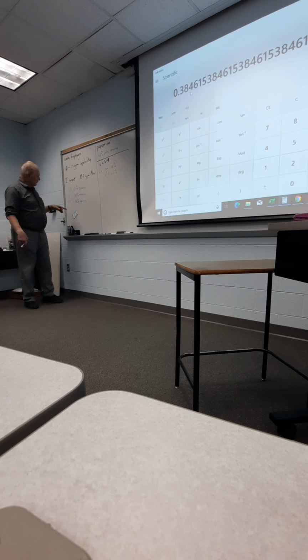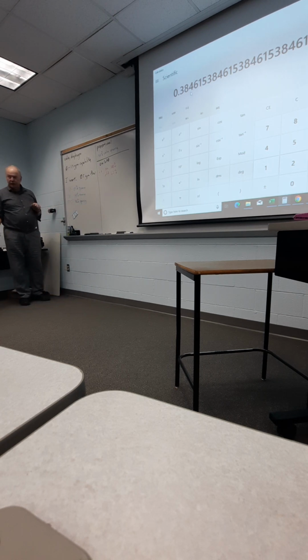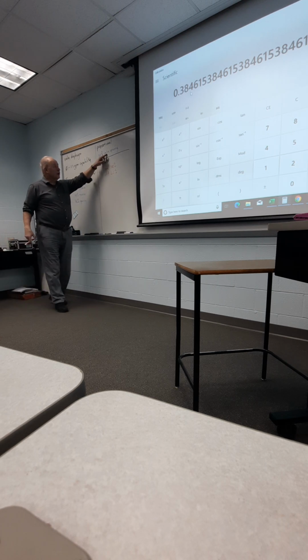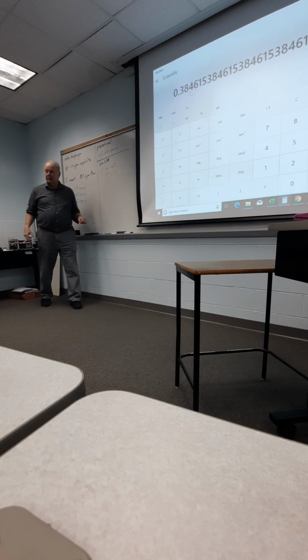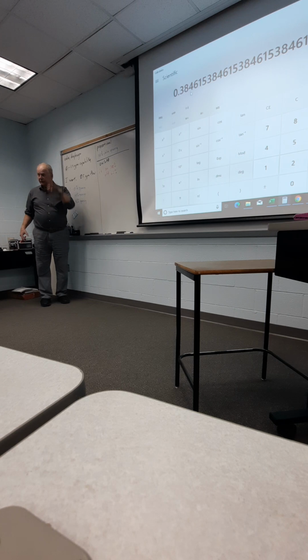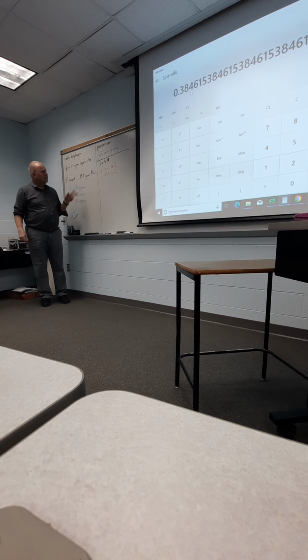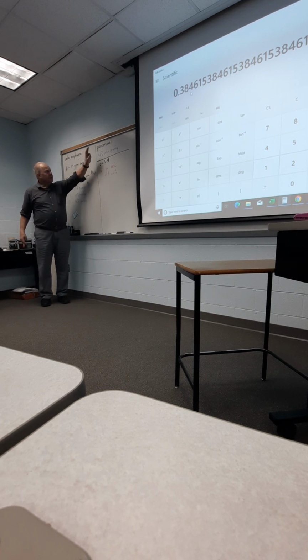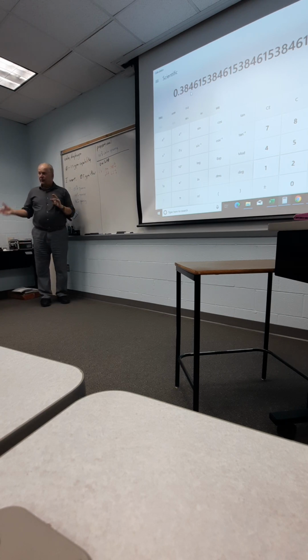In other words, if I want to change the 0.5 to say a 0.7, let's nudge this a little bit more open. Here, we change the duty cycle, but it does still have this little bit of reaction time. It's kind of minor, but in a very large system, we might notice it. But usually you get around to, if you can't live with fluctuations, this is better. If you can, this is definitely cheaper.